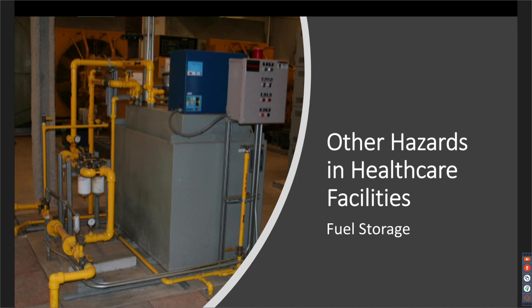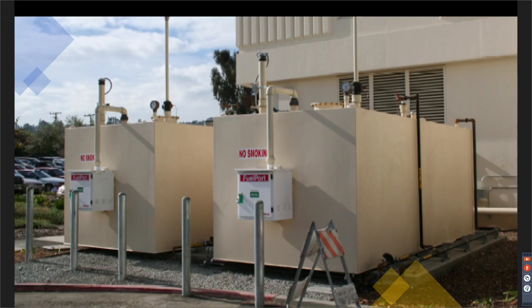The higher you are in the building, the number of stories that you are located, the less amount of hazardous materials that you're permitted to have. So the question often gets asked, can I have emergency generators on the roof? And the answer is yes, but you may not be able to have the day tank on the roof, depending on how high you are. Things to take into account.